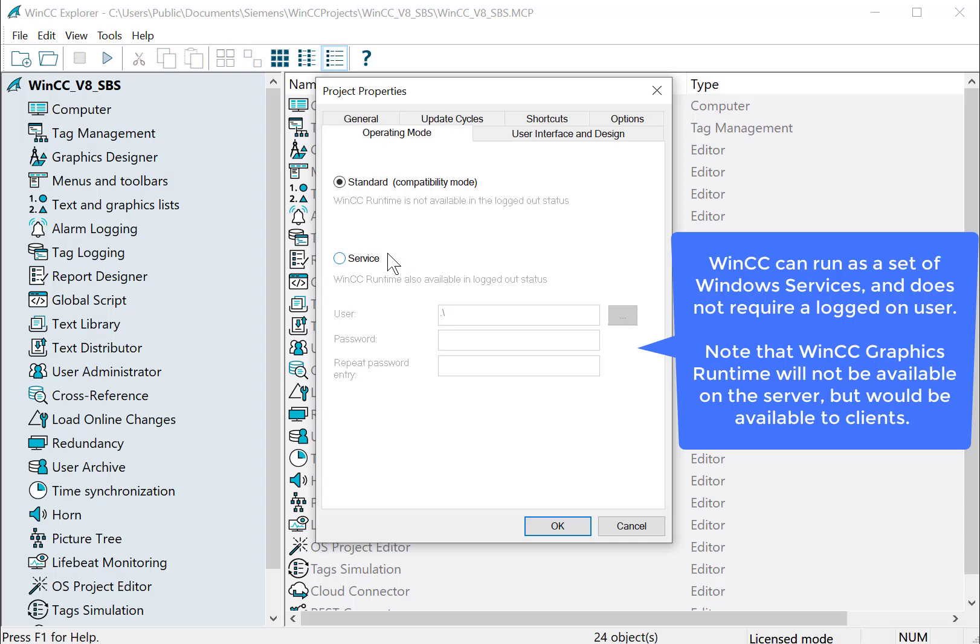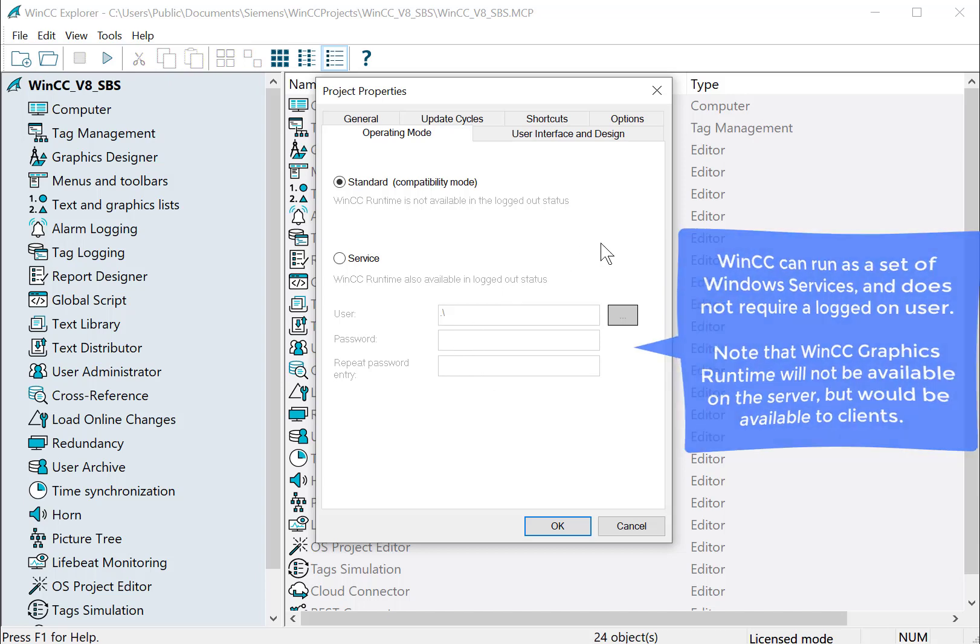And this is not acceptable for certain industries, oil and gas and things like that. And you can run it as a service and you just give it an account to run under. Now you're going to notice if you do run it as a service that no one has to be logged on. And also there is no graphics runtime on the server. You would be seeing that on your client systems. You would also see it on Web UX or Web Navigator, but you would not have a local runtime. It would actually be disabled.